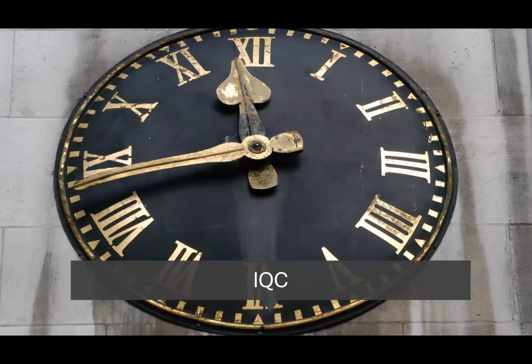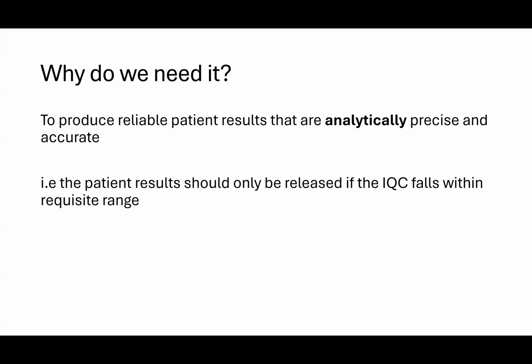In brief, IQC material contains analytes of known concentration that we test routinely during an assay. We know what concentration result to expect, or the range the result should be within. And if the result we get is outside of this range, then we need to consider whether or not we should be releasing the patient results we have that have been tested alongside this IQC. So why do we need it? Why do we use it? We need it to produce reliable patient results that are analytically precise and accurate. And the patient results in most instances should only be released if the IQC falls within the requisite range.